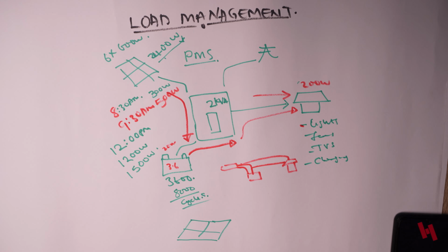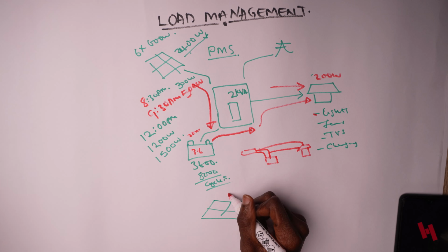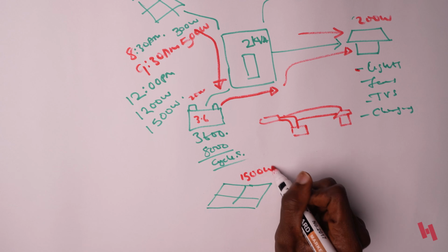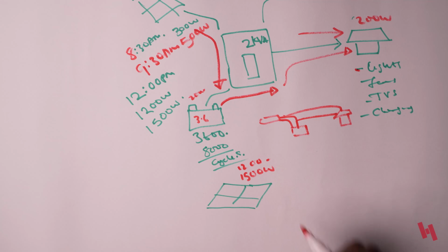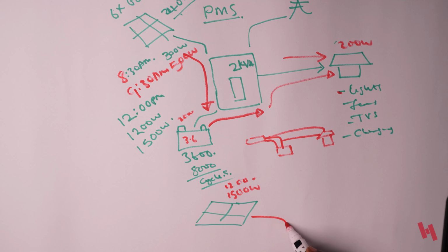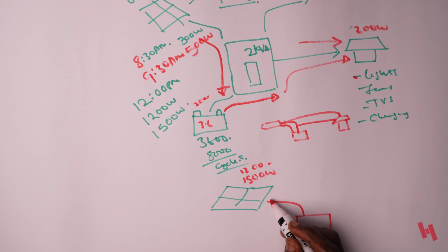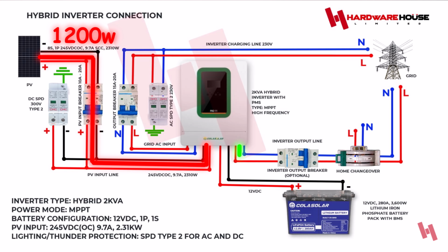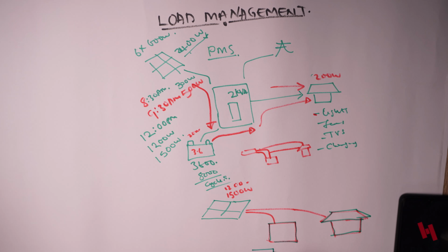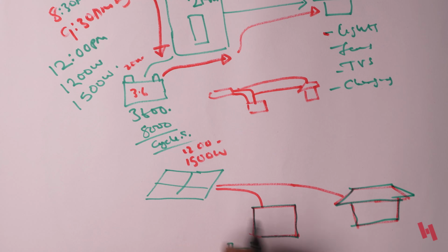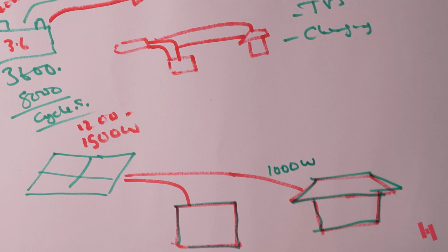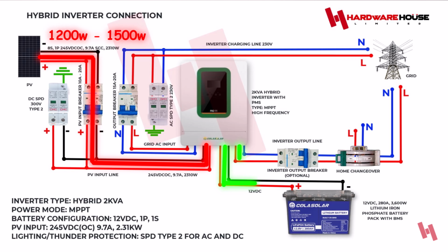At this period in time, this solar panel is giving out 1,200 to 1,500 watts. This power is going to prioritize your consumption. So the power would flow from the panel to the house. Your inverter would use the panel to power the house. This is around 12 noon, 1 p.m., 2 p.m., thereabout. Now, the battery at this point isn't consuming much because it's getting full. If it's 1,500 watts, the panel can put 1,000 watts on the house and around 500 watts for battery charging. That means this battery is resting, it's not discharging at all.